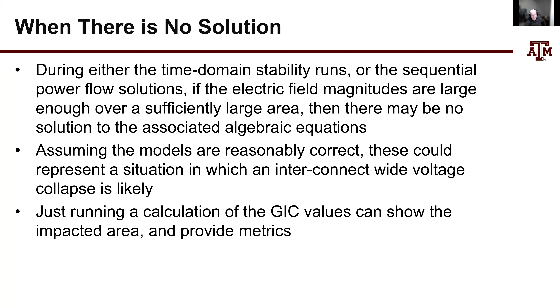We also have the ability, rather than doing stability simulations, to do more approximate modeling, where we just look at the GIC values that we're getting induced in our transformers. So this image here shows the 50 volts per kilometer scenario, not solving stability. I'm not even solving power flows. I'm just running the time and spatially varying waveform and calculating the GICs on the transformers. And you can kind of see the values there. These are the per phase effective GICs that we get.